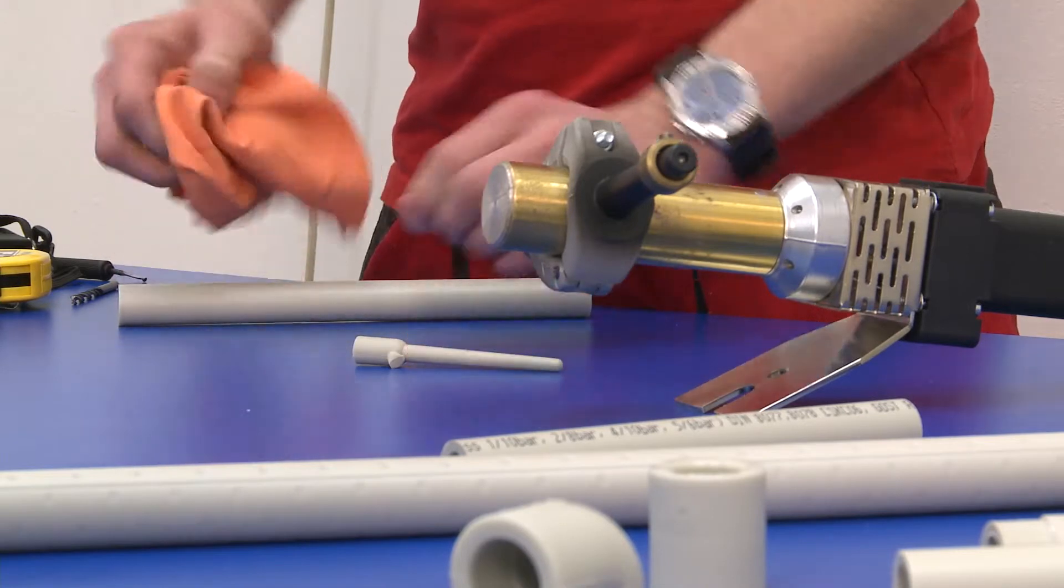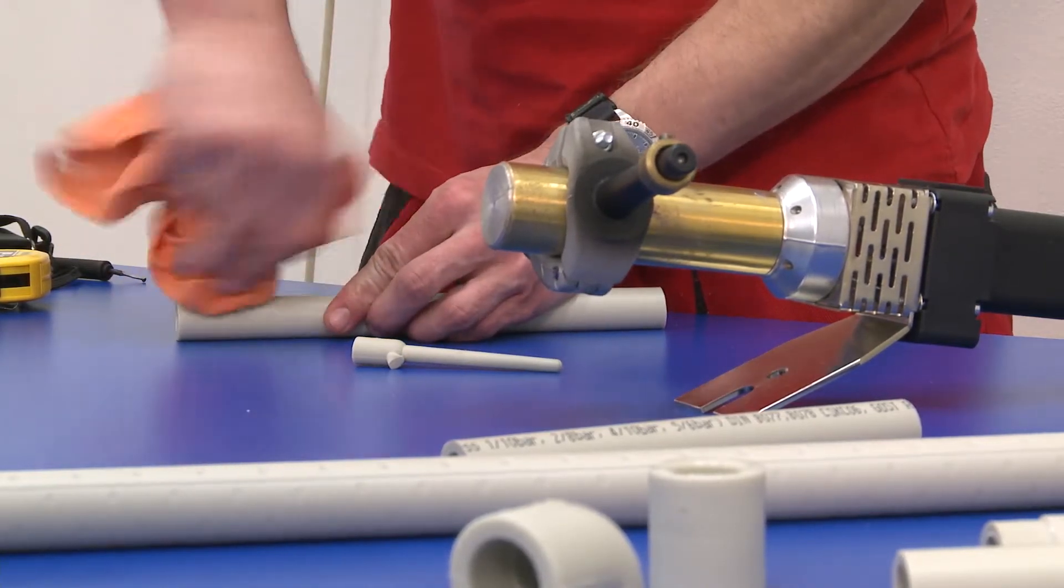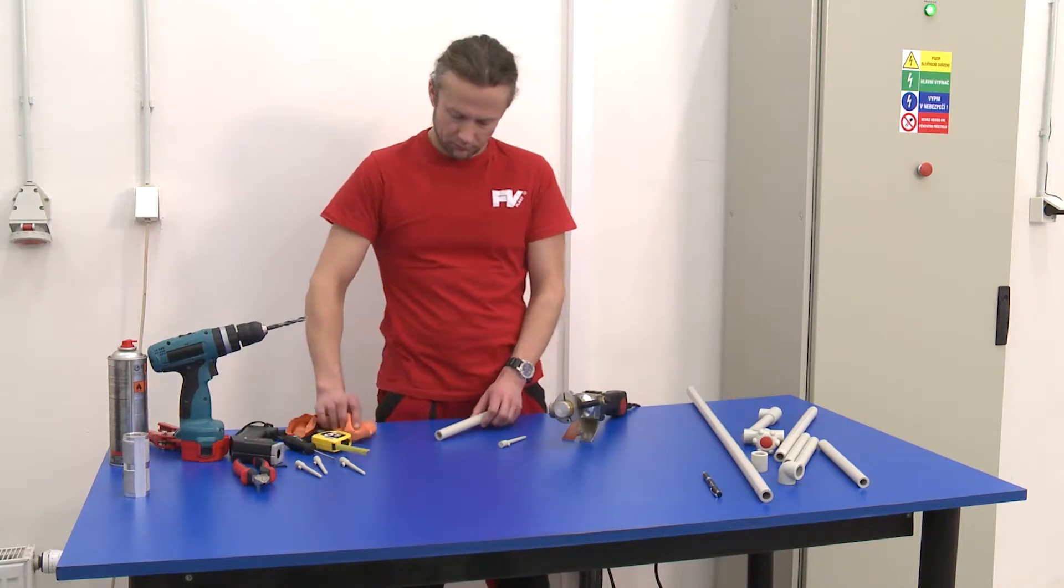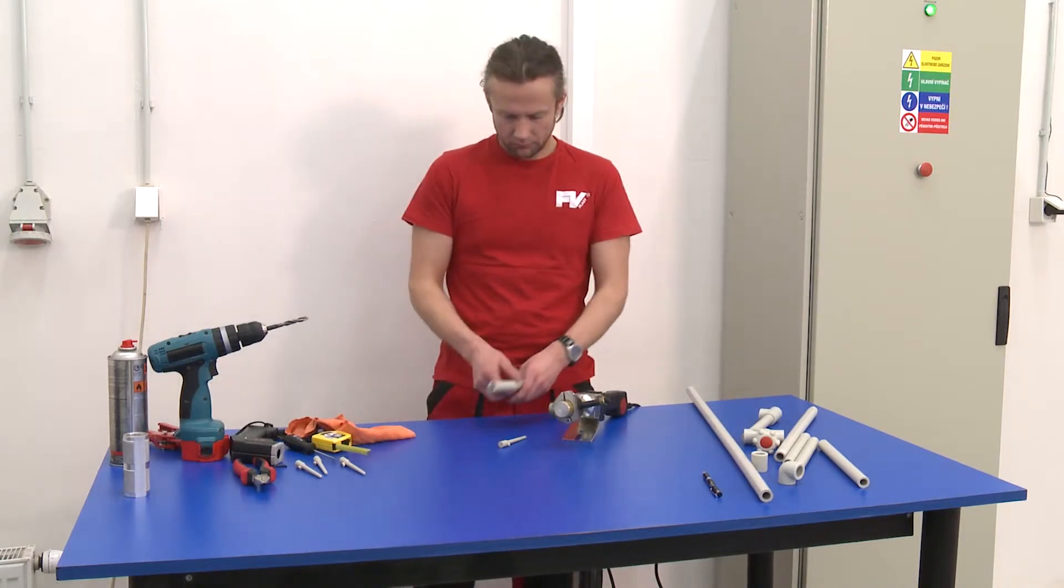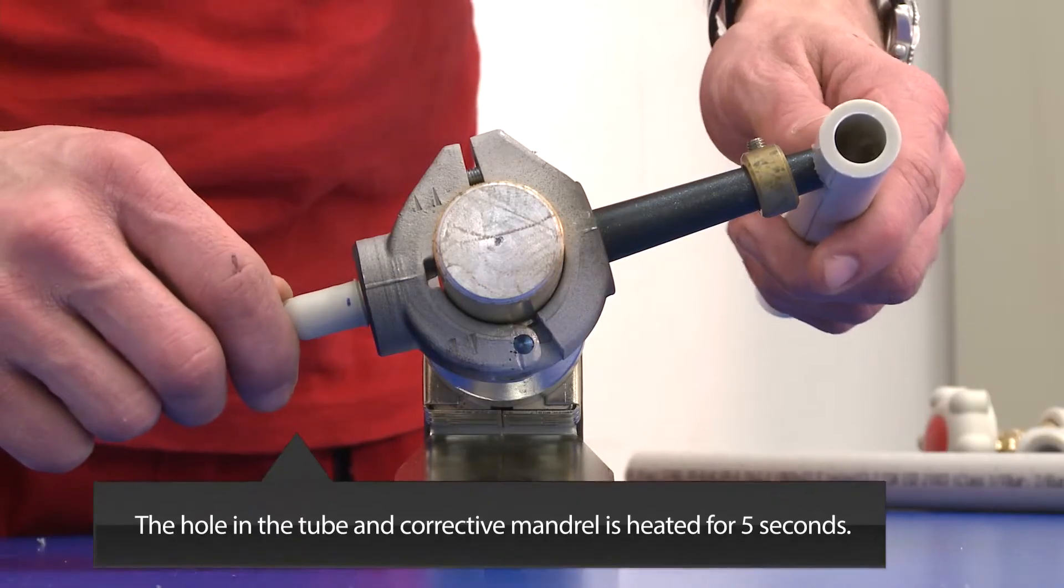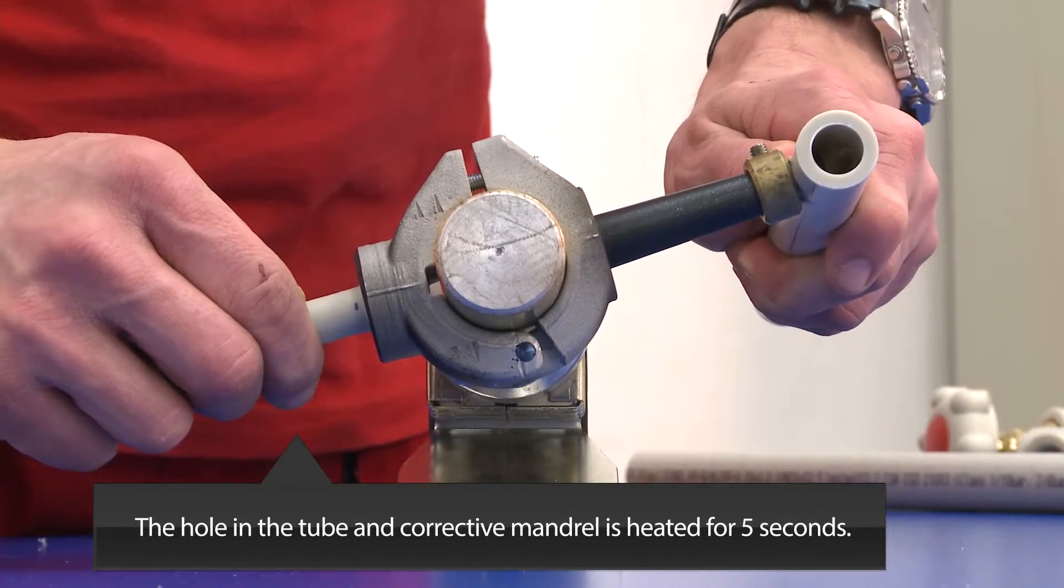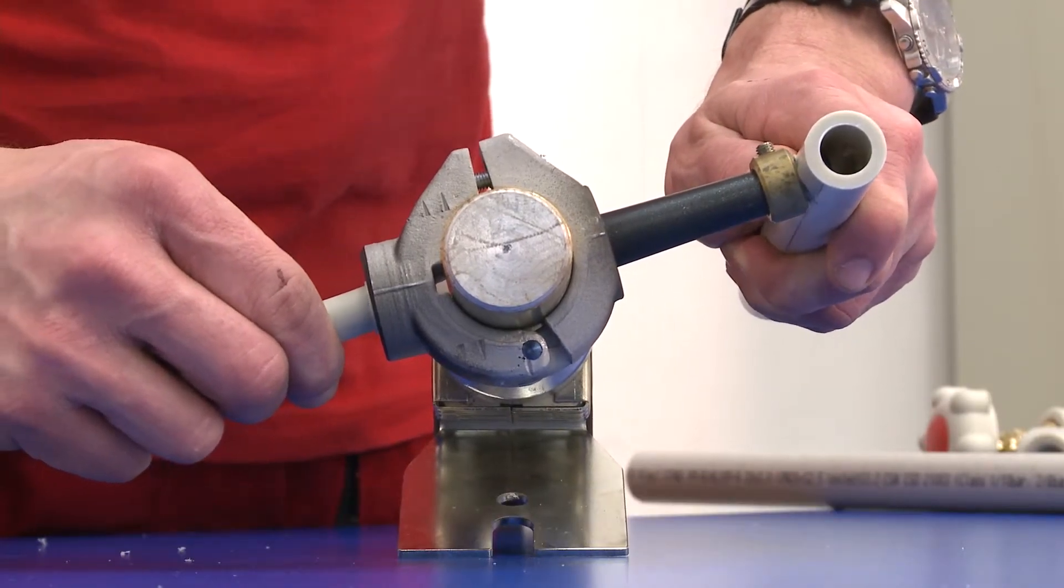When working it is very important that the contact surfaces of the corrective mandrel and the hole are dry and free of grease. The hole in the tube and the corrective mandrel are warmed up simultaneously for five seconds to create a melting collar as during normal polyfusion welding.